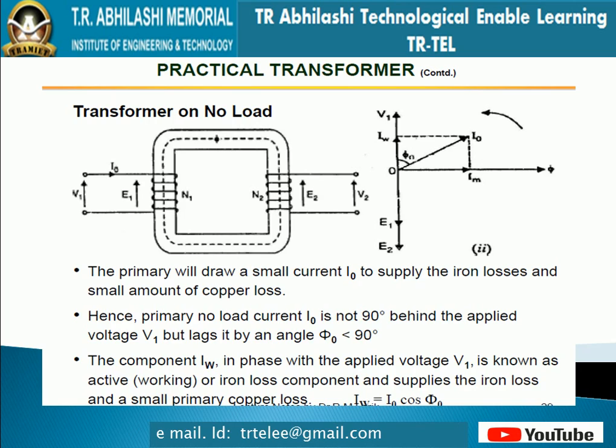As V1 is the applied voltage, there should be a current I1 that would normally flow, but there is a small current called the no load current. I0, the no load current, will flow, and it is not 90 degrees phase behind, but something less than 90 degrees phase behind the applied voltage V1.